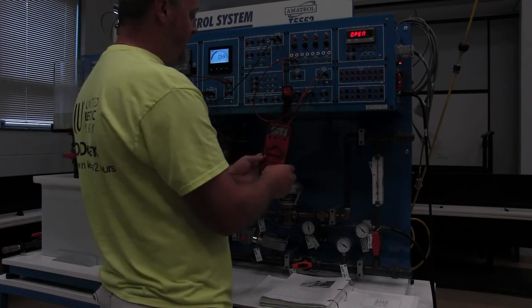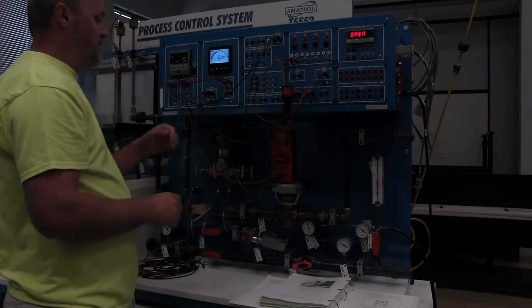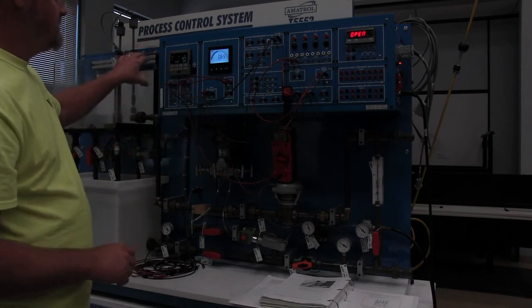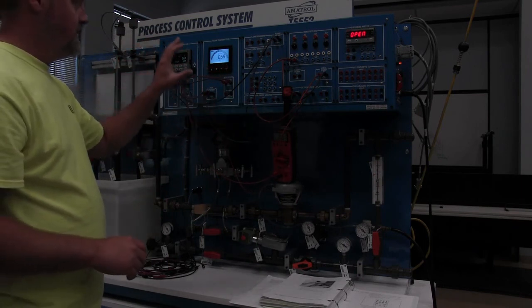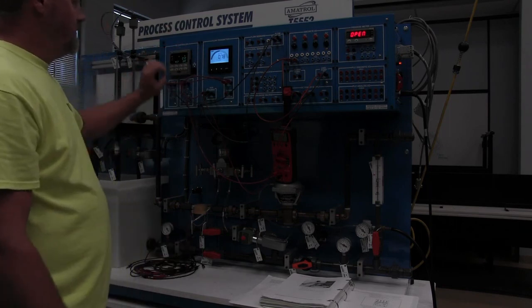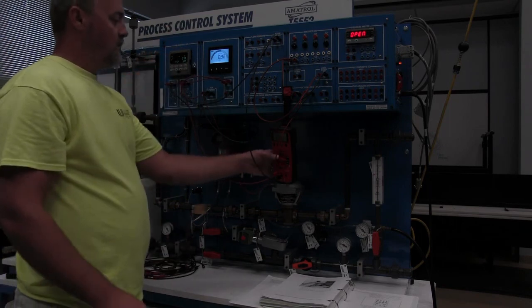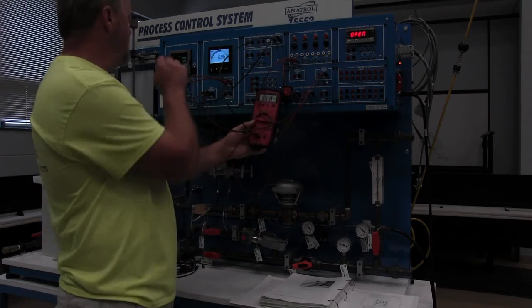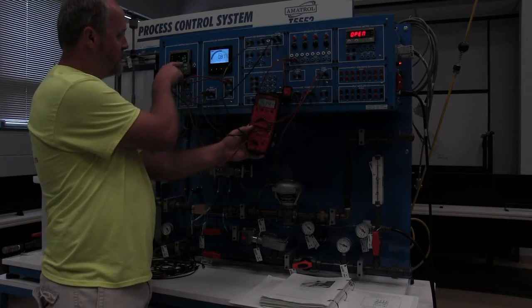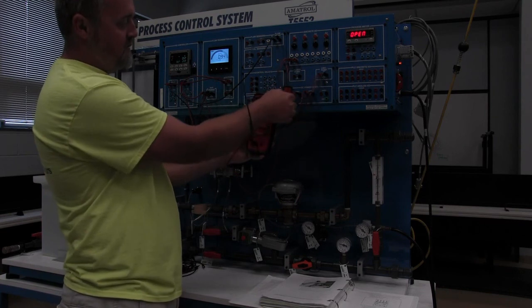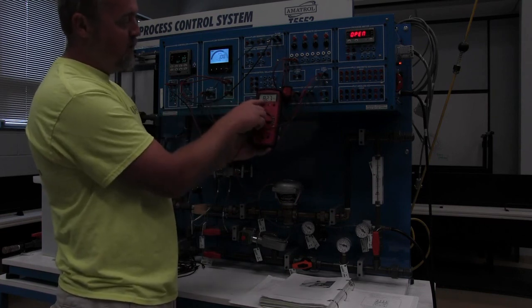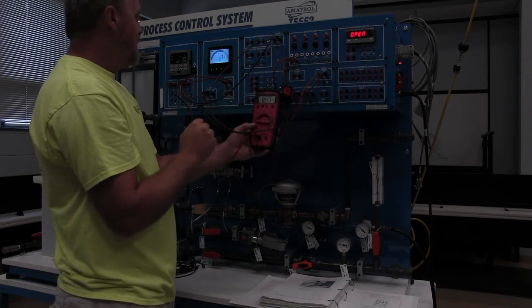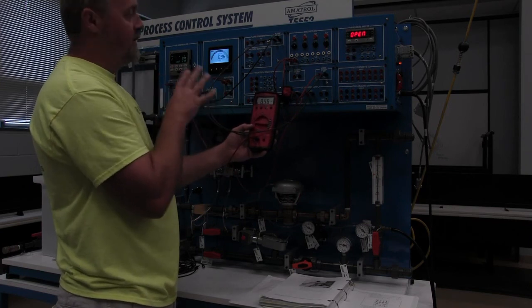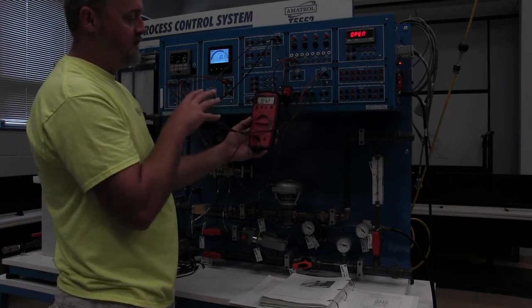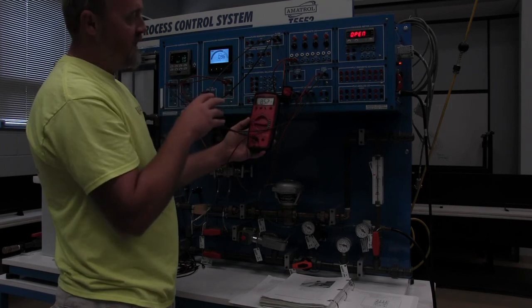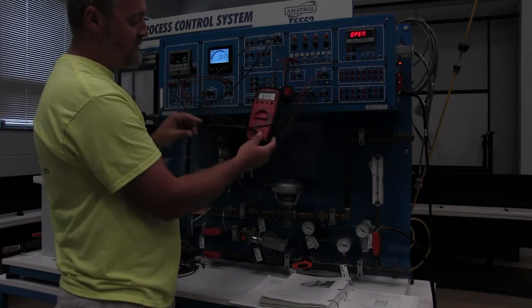So basically what I've done now is I've put this meter in a series loop with the output of this controller. So what you'll see is as this output is decreasing here, so is my milliamp signal here. I'm at an 8.4, 8.3, 8.2. So if you were wanting to read in a milliamp signal of what was going on inside your circuit, all you have to do is just series this in.